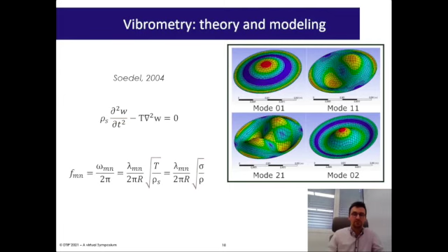What we can see is that the resonance frequency depends on the stress, here sigma, of the membranes. Similarly to the microbending, we simulated by finite element analysis the elliptic shape of the membrane to quantify the impact of the elliptic profile on the mechanical dynamic behavior. For that purpose, we perform vibrometry to identify the resonance frequencies of two membranes.